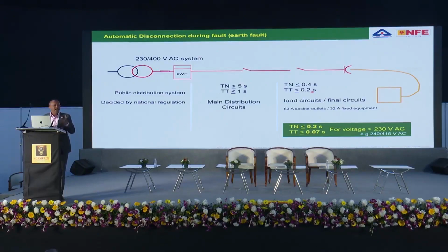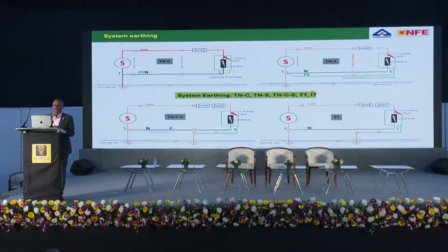So basically, having a protective device is not important. Having a protective device which is doing its job, which has to trip, is much more important. I have investigated several fire accidents as well as shock accidents. In 90% of cases, the protective devices are there, but they are so strong that they are not able to trip, due to several reasons. Sometimes dust, sometimes oversized, sometimes no testing, no return path. Several reasons are there. Basically, the electrical safety engineer should ensure that equipotential bonding and disconnection of these devices within this time is very important.